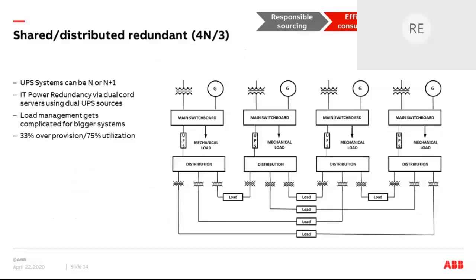Downstream, we have individual UPSs, where from left to right, A and B share a load, B and C share a load, C and D share a load, and A and D share a load. This allows you to support the loads without that 50% overcapacity. So we have 1 extra genset and UPS, or 33% over-provisioning, and our utilization is at 75%. We've significantly improved what we use in critical power equipment without giving up too much in availability and reliability.